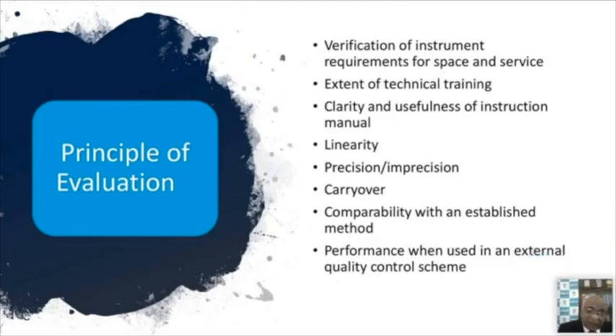This analytical sensitivity is also very important. Analytical sensitivity is different from diagnostic sensitivity. It is the minimum difference which a machine can appreciate for a particular analyte. Suppose your machine is measuring glucose. One machine measures 100, 110, 120, 130 or 140. Another machine 101, 102, 103, 104. A third machine 100.1, 100.2, 100.3, 100.4. The difference which a machine is able to appreciate is called analytical sensitivity. In the first machine it is 10, in the second machine it is 1, in the third machine it is 0.1. So you have to see what your requirement is.